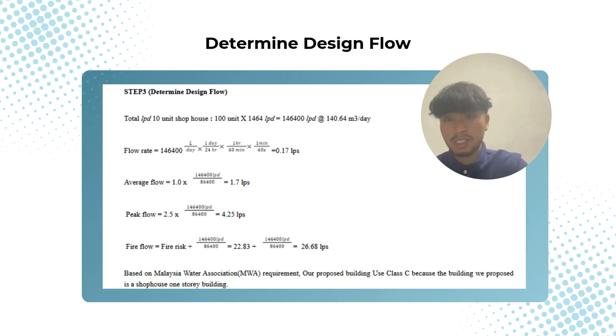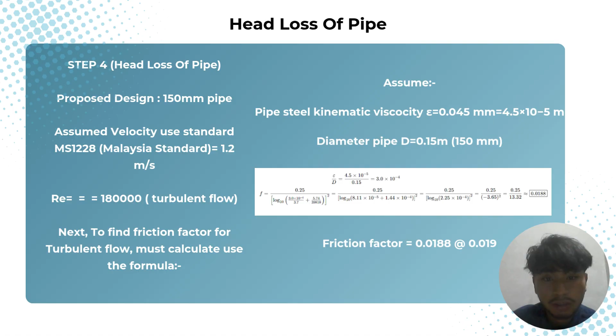Okay, for the head loss of pipe calculation, the proposed design is a 150 mm pipe. We assume velocity using MS 1228 Malaysian Standard, 1.2 m/s. So we calculate the Reynolds number and get 180,000, which is turbulent flow. Next, to find the friction factor, we assume pipe roughness 0.045 mm, or 4.5 times 10 to the negative 5 m. The pipe diameter is 0.15 meter, equal to 150 mm as before. Using the stated formula, we get a friction factor of 0.019.